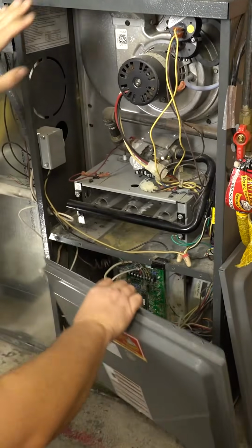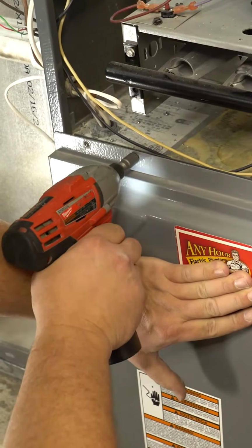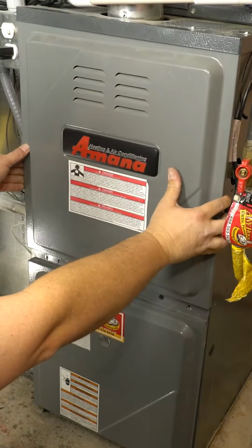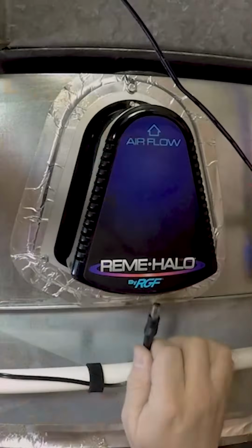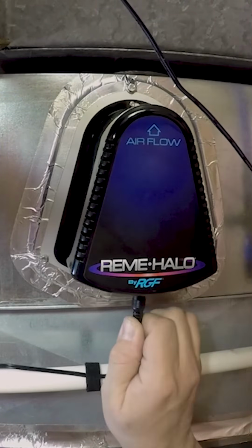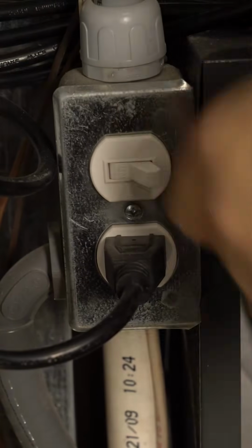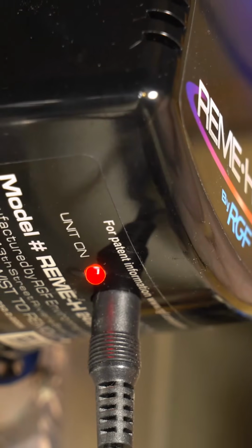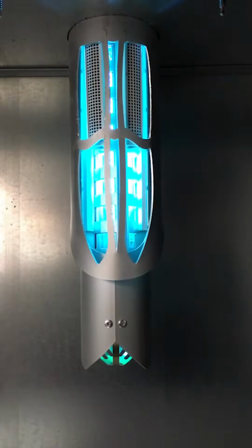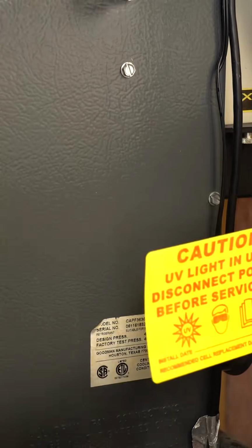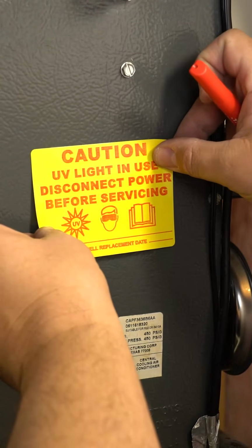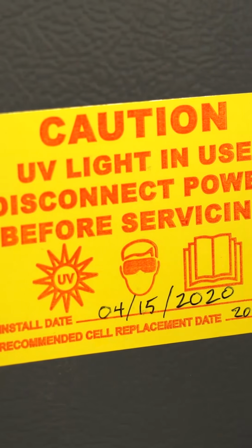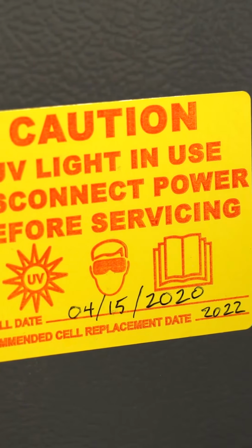We should be done in the furnace cabinet, so I'm going to go ahead and put the doors back on and button that up. Plug the power cord back into the Reme Halo unit and power the furnace back on. You should see a red light indicating that the unit is on. Fill out the UV caution sticker and apply it to the ductwork. It's recommended to replace the cell every 2 years to maintain the optimum effectiveness of the unit.